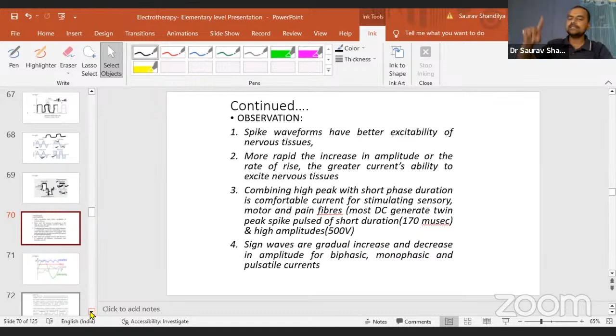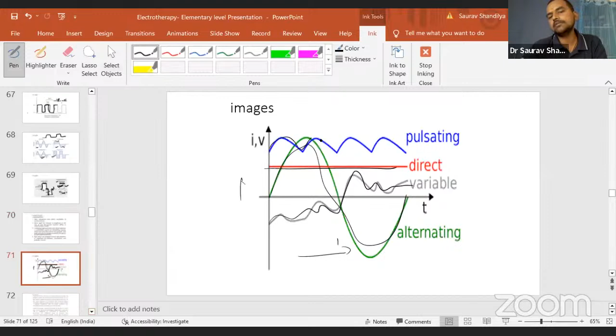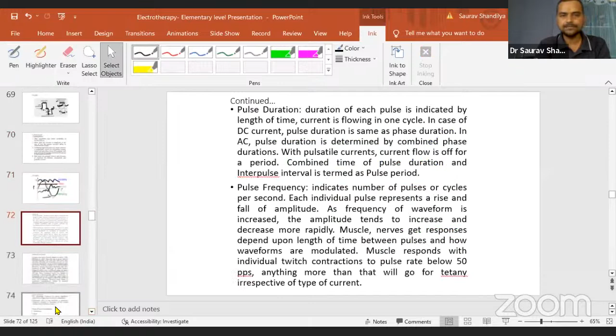Sine waves have a gradual increase and decrease in amplitude, for biphasic, monophasic and pulsatile currents. So this is where I have shown the basic idea. It is self-explanatory. Again, you can see intensity or voltage on the y-axis and time on the x-axis. This is the alternating current, which we call biphasic. This is variable, sometimes down, sometimes up. This is a direct current, and pulsating is always like this, pulsatile current. Most of the time we are using the pulsatile. Pulse duration and pulse frequency mean how many pulses there are in a second.